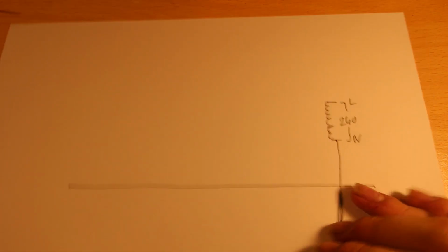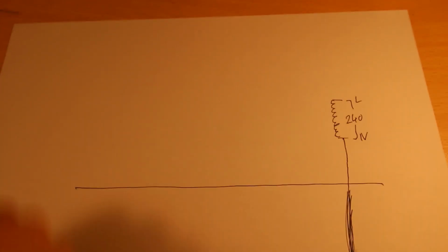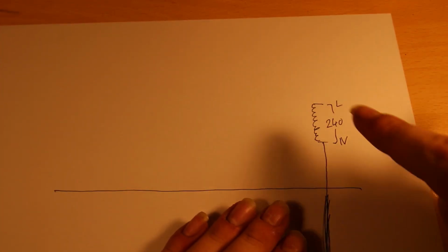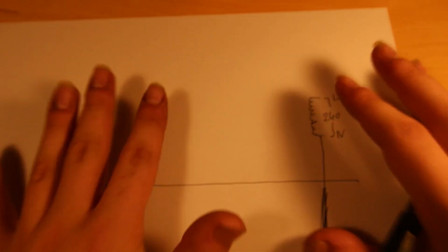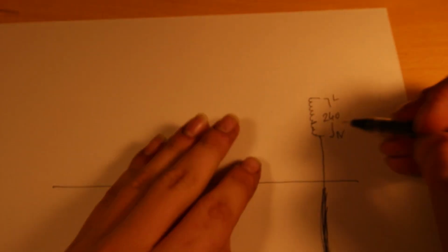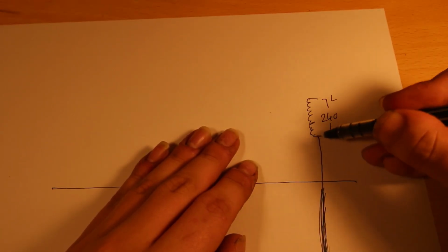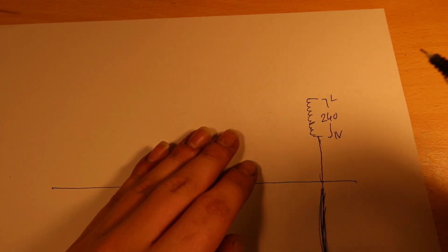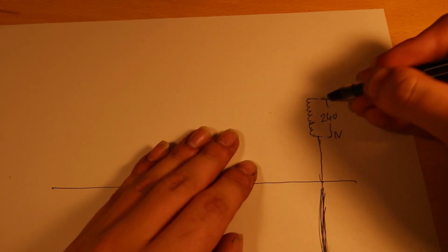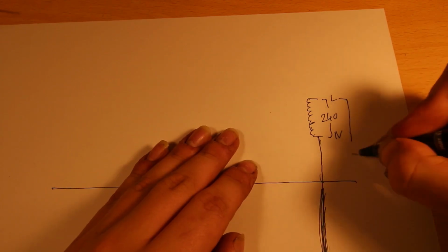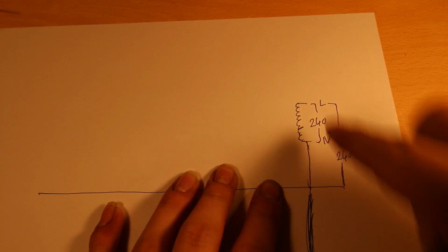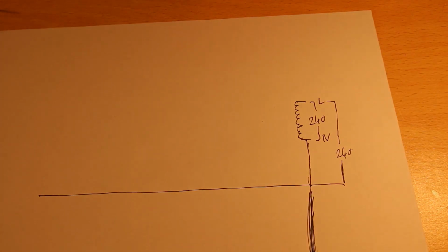This is why people go, oh, AC polarity doesn't matter. Yes, it does, and this is why. If you touch the neutral, you shouldn't. I will stress this. You should under no circumstances touch a neutral. It is a live conductor. But it is usually, provided everything is working, very close to Earth potential because they are connected at the substation. But the live is 240 volts above neutral, so you have 240 volts between here and here. Which means if you are unfortunate and you're standing on the Earth, so you're connected here, and you touch that, you'll get a massive shock.